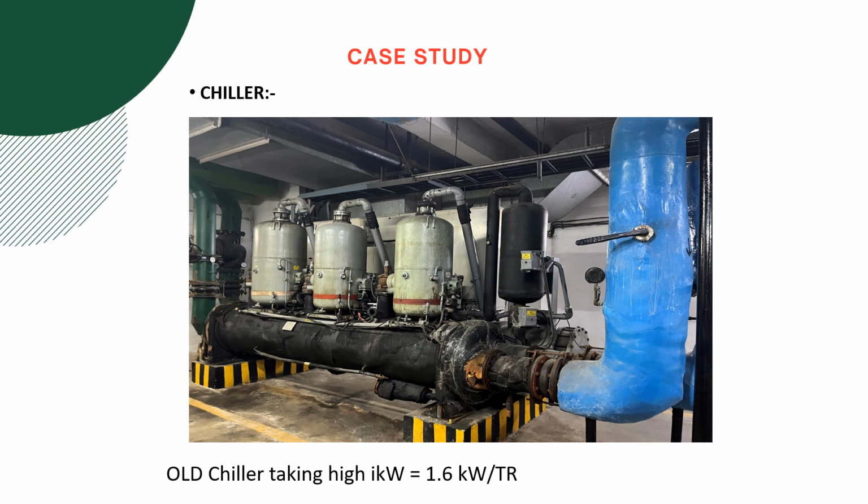So we'll do a case study of a chiller. Here you can see this is the chiller which was present in our site, which was a commercial building. It was a mall. So this was an old chiller, like 20 to 25 years old. As it was old, here you can see these are the compressors. These are cylindrical type compressors. Nowadays screw type compressor is being used mainly in chillers.